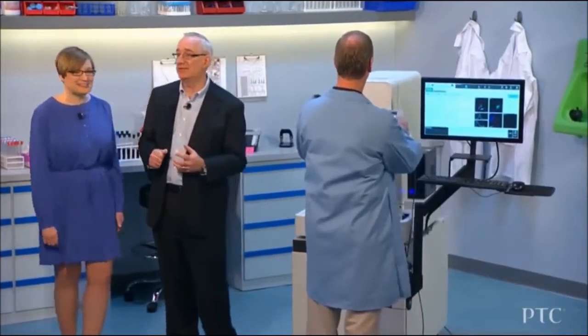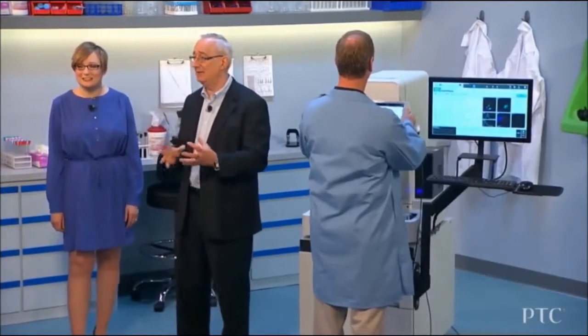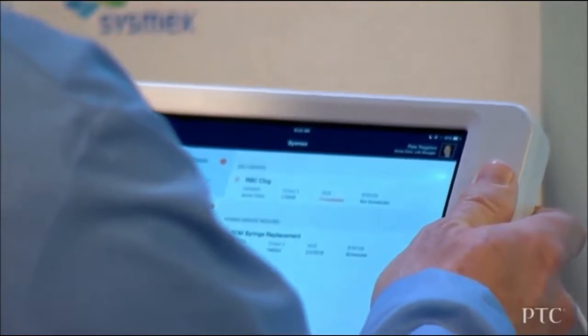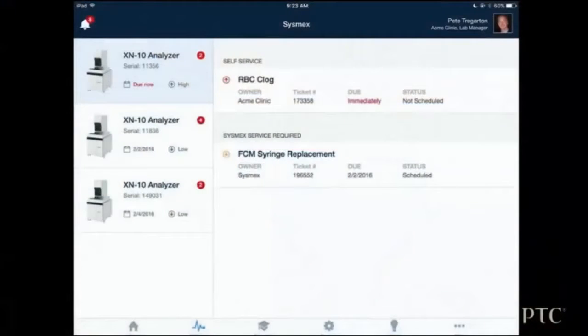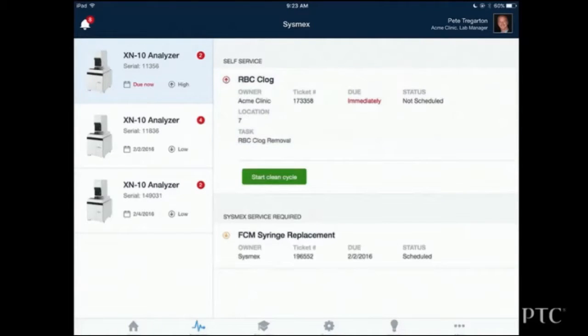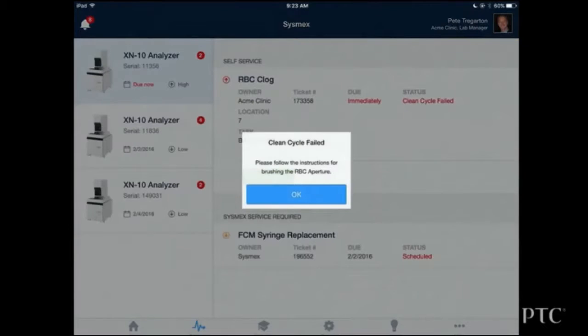Well, here we see a list of all the analyzers that Pete has in his lab. Notice that he's selecting an analyzer that has 2 service tasks to be performed. One requires a Sysmex field service engineer. The other can be performed by the operator. Pete selects the RBC clog and begins walking through a series of instructions. His first task is to initiate an automated cleaning cycle. He simply selects Start the Cleaning Cycle on the iPad.